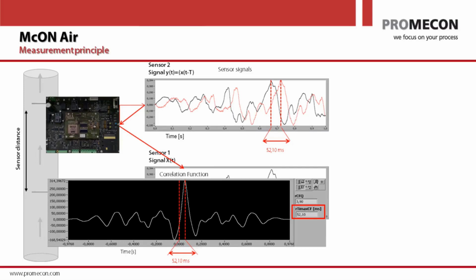So you have an overlap of sensor 1 and sensor 2. And if you measure the overlap and then you shift the signals towards each other in time, then the overlap will be different. And at one point, when the signals basically overlap perfectly, you will have this maximum in the cross-correlation function. And the time that you can see in this cross-correlation function is basically the flight time from sensor 1 to sensor 2. So by doing this cross-correlation, you can calculate out of these two raw signals at which time shift we have the maximum overlap. And this time shift is our time of flight.